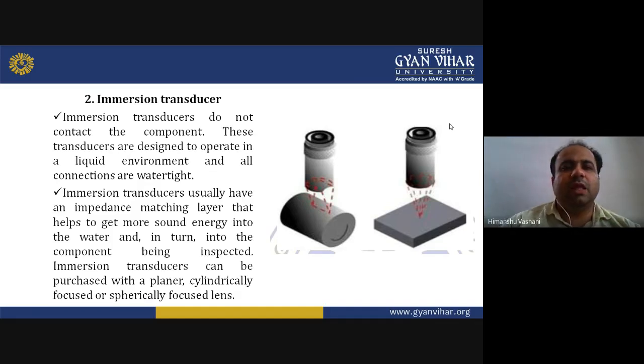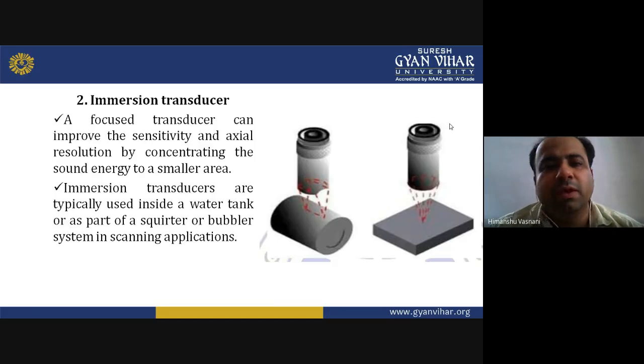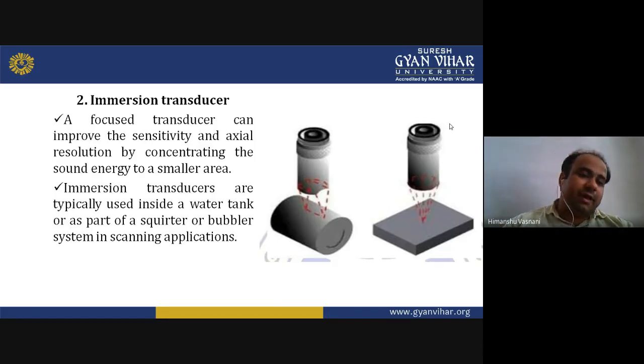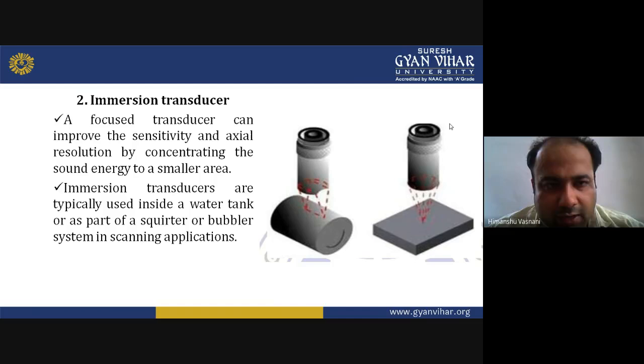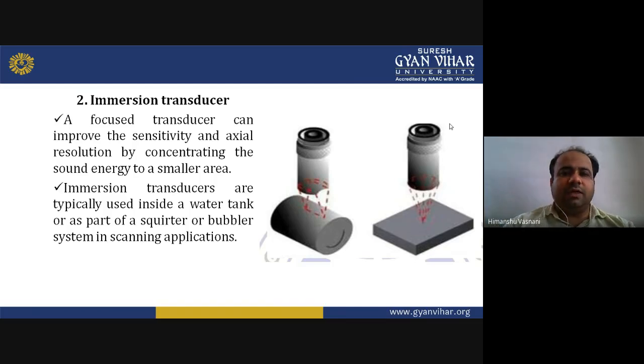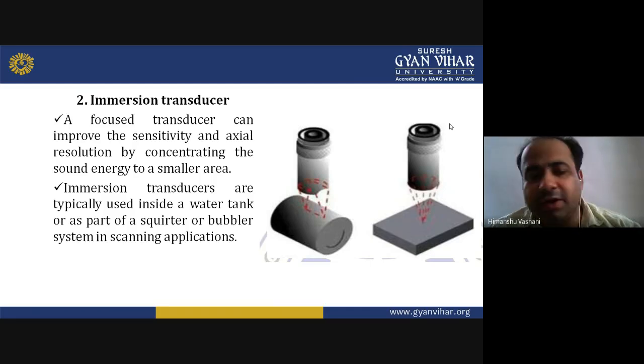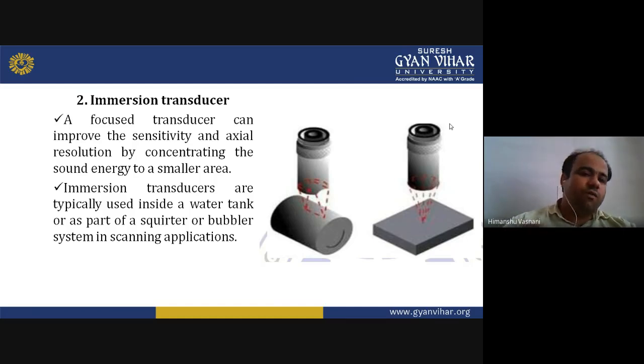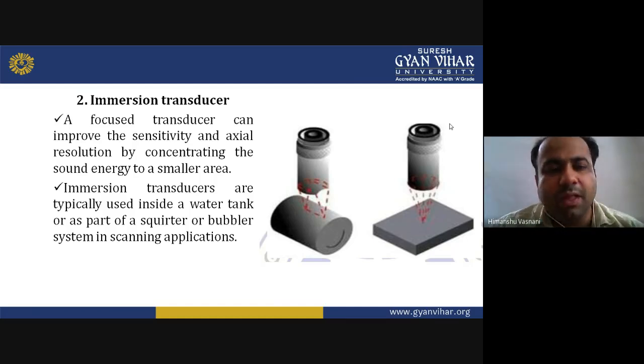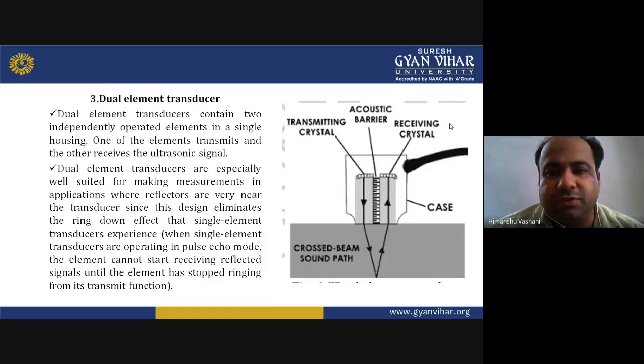Now, a focus transducer can improve the sensitivity and the axial resolution by concentrating the sound energy to a smaller area. You can see that the focus transducer is very important. As the name says, focus, you can focus on a particular area. These immersion transducers are typically used inside a water tank or as a part of a squirter or bubbler system in scanning applications.